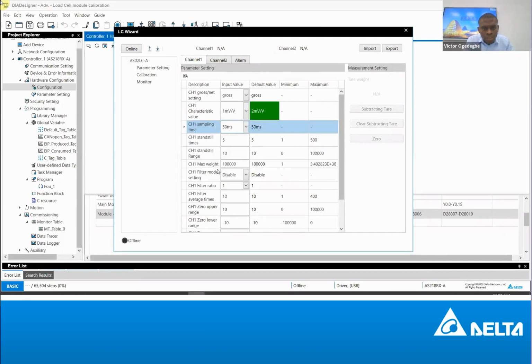And then you see these are other functions, like standstill. You see maximum weight. The maximum weight is like the maximum digital value that you can set. So 100,000, you understand? If you set this maximum, it means when the sensor measures its maximum, the digital value is the maximum you have set. It is quite tricky, but I think you got it. I don't know if you can go beyond that, but the default is 100,000. So I can say 100,000 for 10 kg, for example. It means if my sensor is measuring 10 kg, the module will give me 100,000.